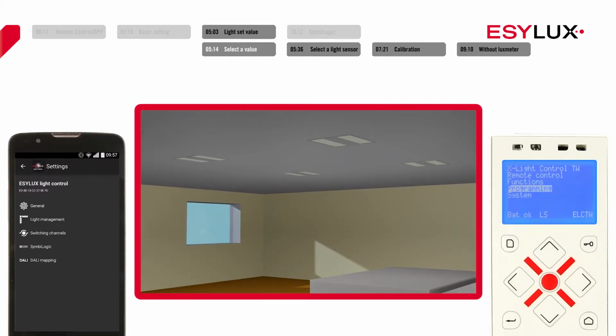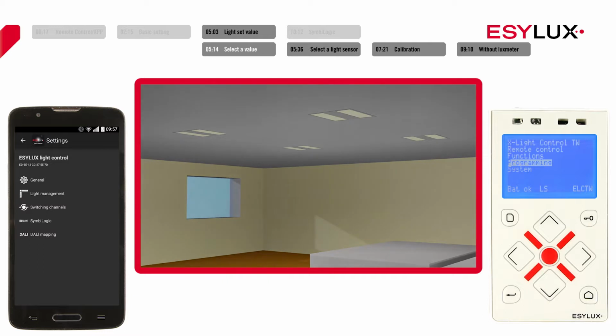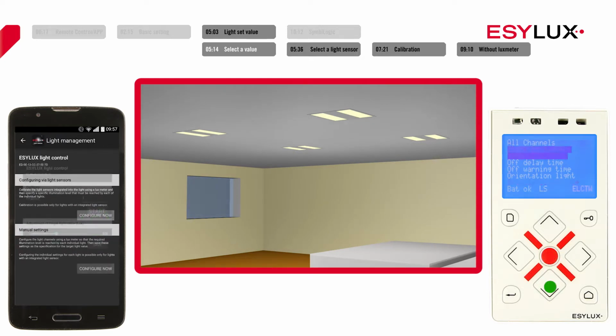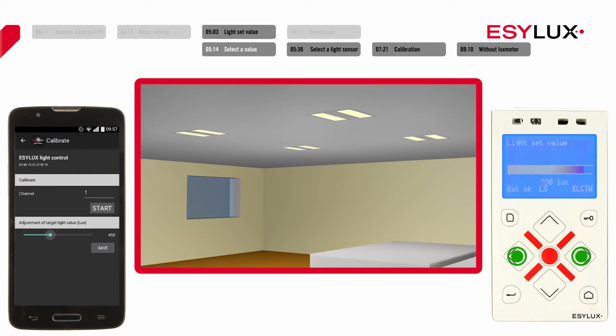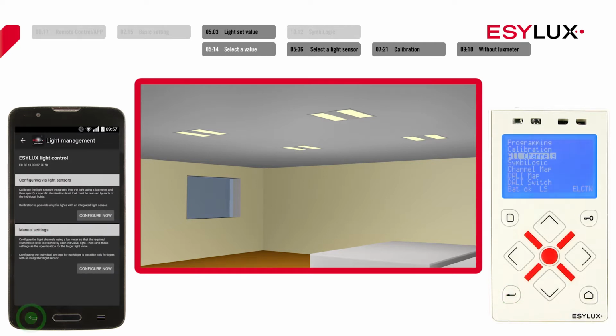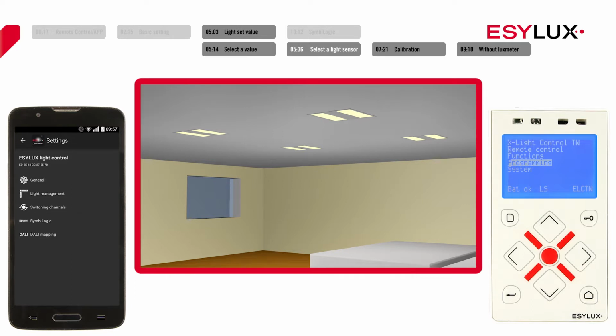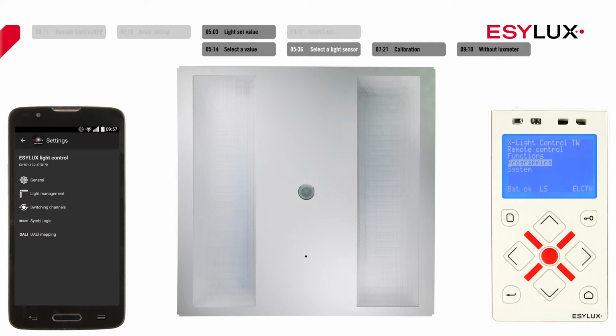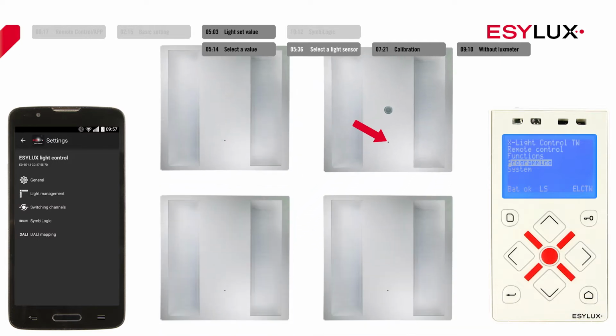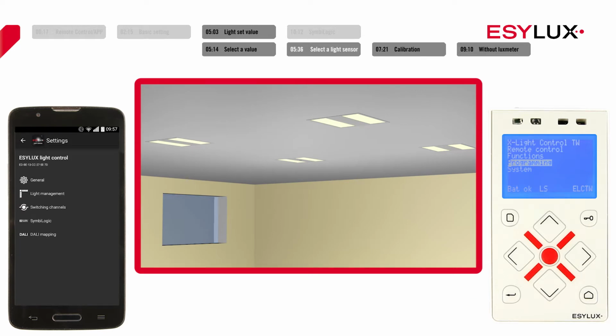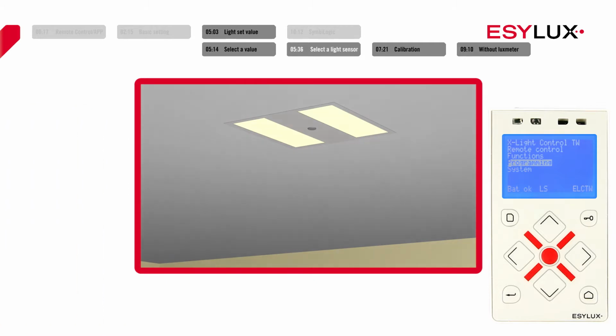If the ambient light level is below the preset target brightness, the master light controls the illumination level. You can specify the light target value as shown in the display. The light must be calibrated for you to be able to control it accordingly. Every presence detector has a light sensor, which you can use to control the brightness of a room. Nova lights are also available with additional light sensors. These lights can detect and adjust the brightness of a room with even greater precision. If you use lights without additional light sensors, then make sure that the light sensor of the presence detector is activated.